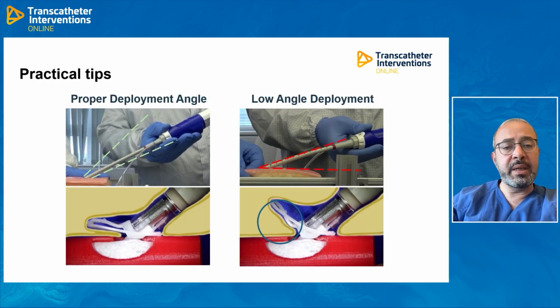There are a few practical tips that we started to learn through our experience, which is of course still limited. But one important tip, which applies to both venous and arterial side, is the proper deployment angle. So you can see here on the right-hand side, the low angle deployment, which may lead to some malapposition between the patch and the anchoring device, which can lead to suboptimal hemostasis or even dislocation of the device. So the proper deployment angle is a little bit higher than we're used to. So it's around 45 degrees. And this is important while applying traction to the device, and most importantly, while applying the anchor of the device.